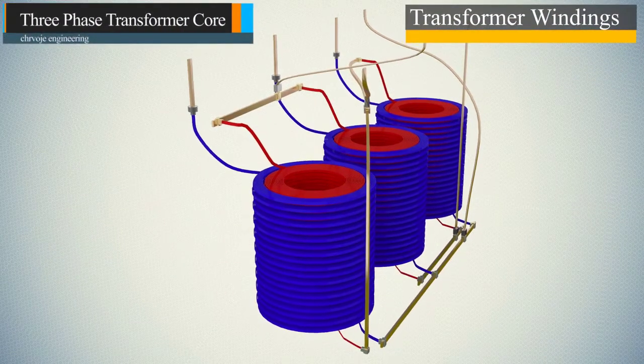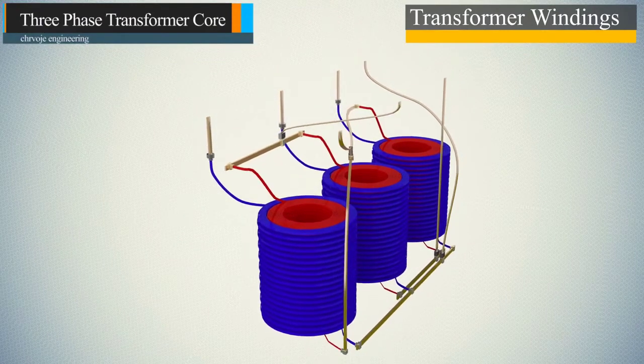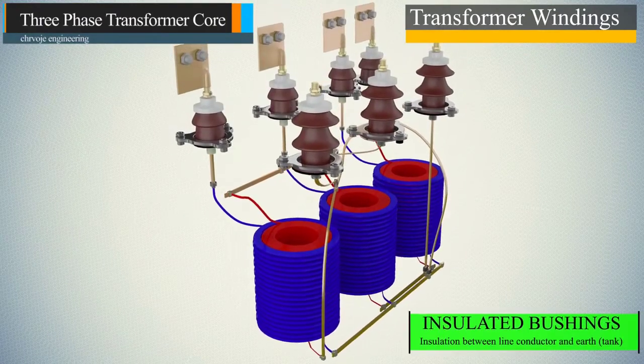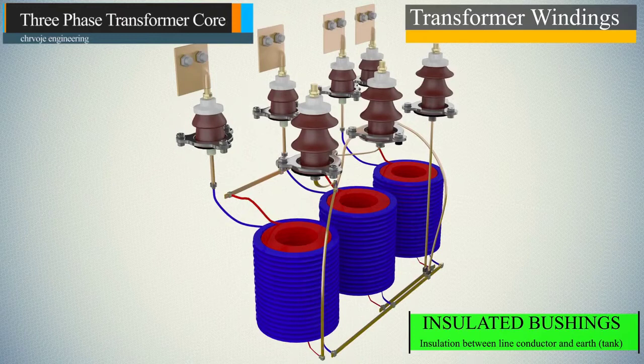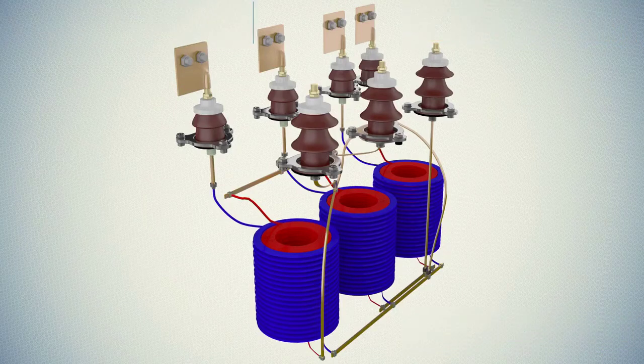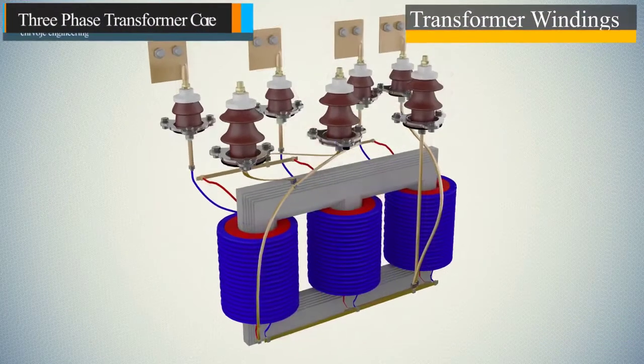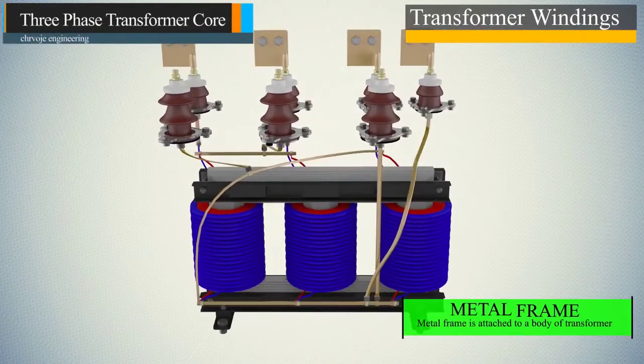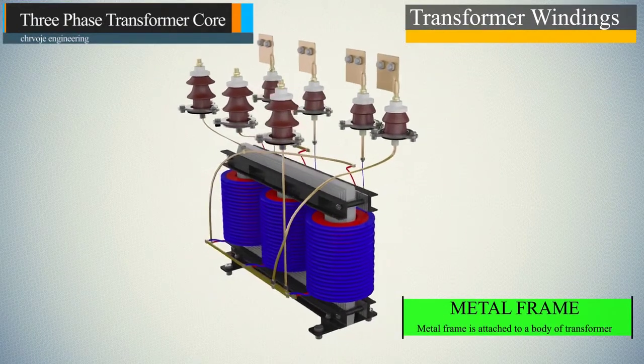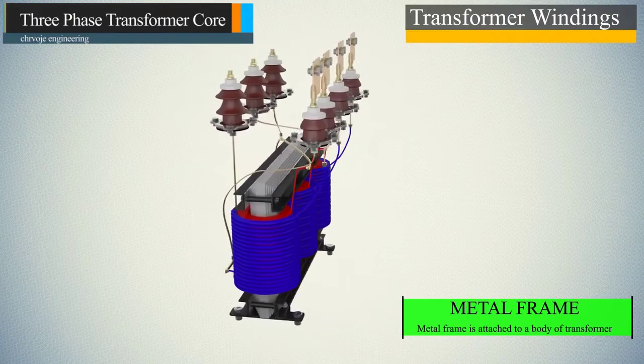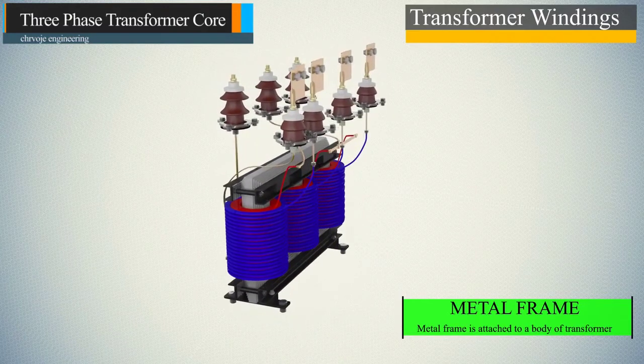To receive or bring out electric energy from transformer, we need insulated bushings. Transformer bushings provide a very effective insulation between line conductor and earth tank. The transformer core is mounted on a metal frame, with flanges extending along the bottom of the frame. The purpose of the frame is to support the coil and to relieve stresses and reduce the no-load electrical losses. A metal frame is attached to the body of the transformer.